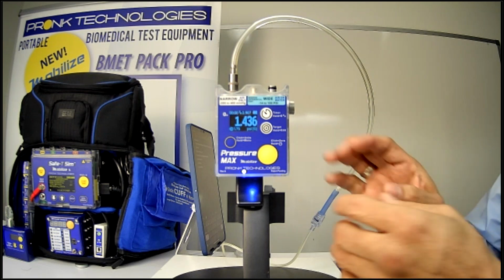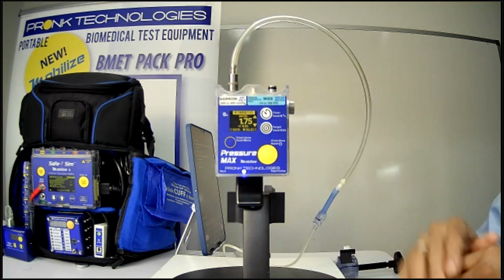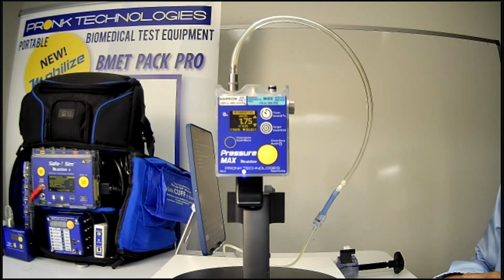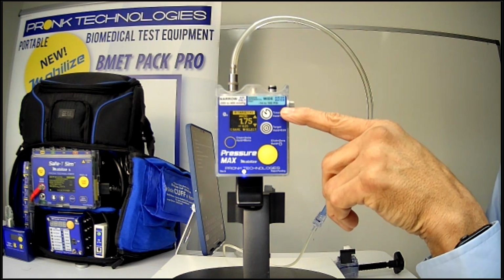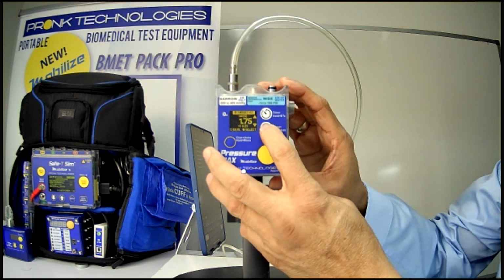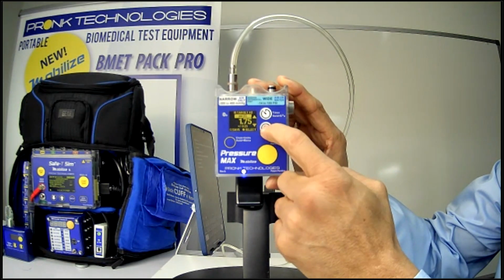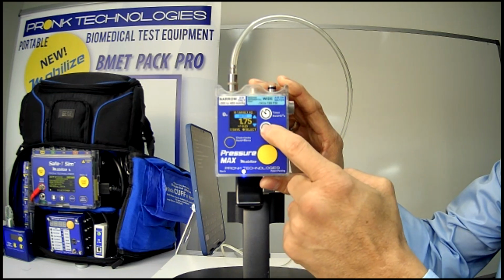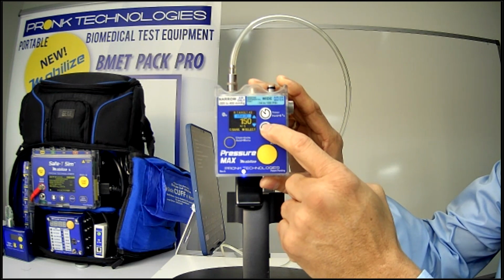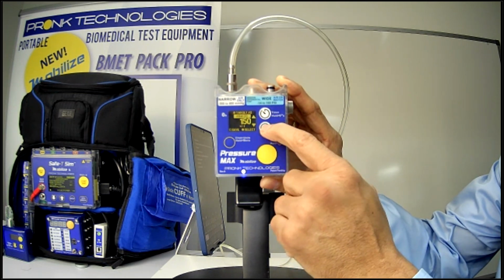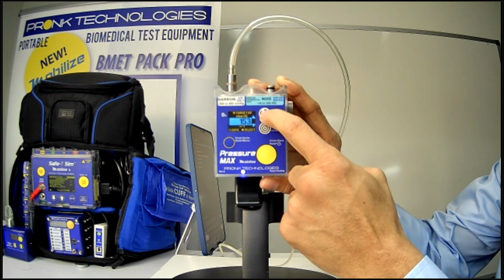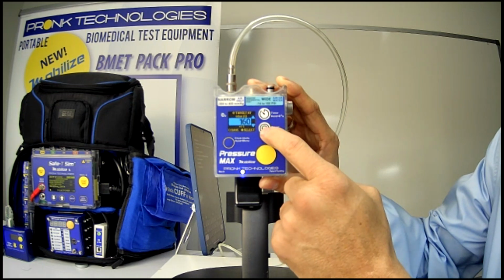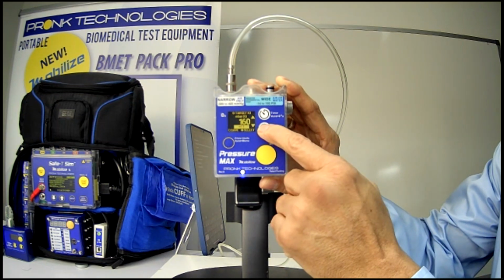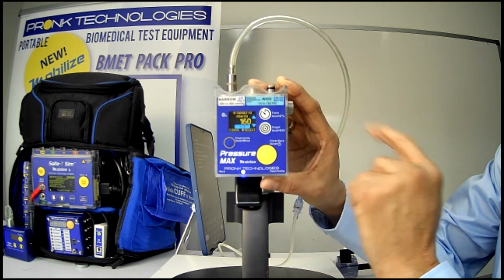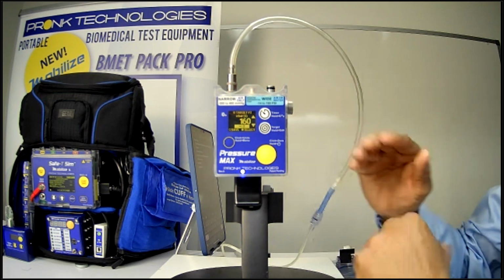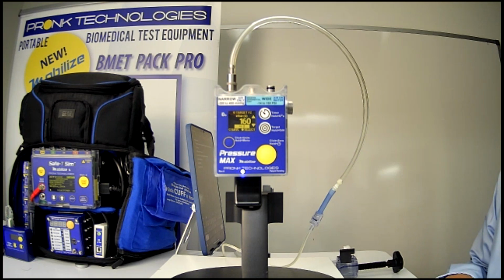And you can program these on the unit, which is really nice. If I press and hold this button here, I can go into my target menu and create and edit target pressures. You can see here at the very top, I'm editing target number 2, and I can edit those values. I can scroll down using the up and down arrow keys that correspond to the soft keys, which would be these keys here. I could change my unit of measure by highlighting it, and then using up and down to change it. So I could pick a different unit of measure if I wanted to. Then I could also confirm and program the actual target pressure. If I want to change that target pressure, I can just scroll up. I can hold it down so it'll advance much quicker. And I can also edit the target tolerance. Here I could change that target tolerance to whatever value I need. So it's really easy to program target pressures with target tolerances on board the unit.